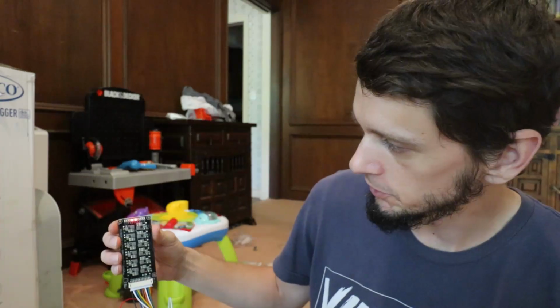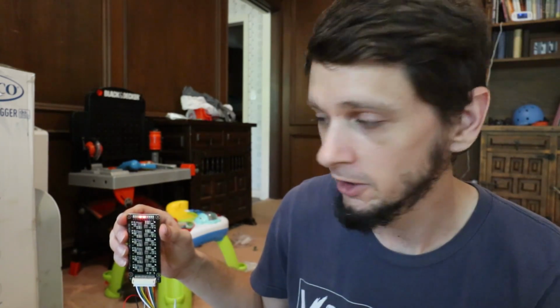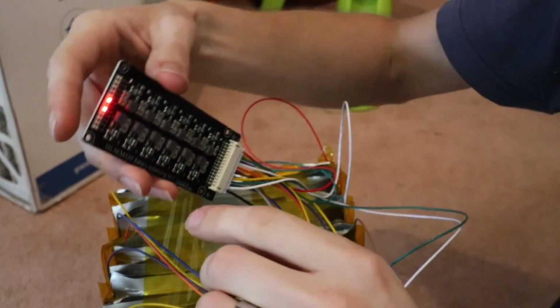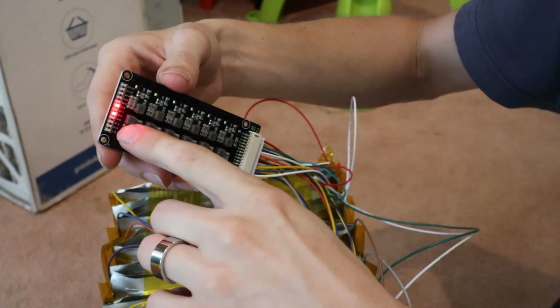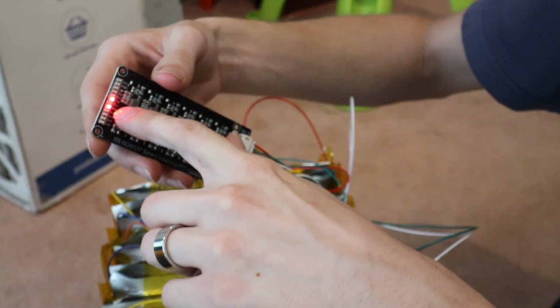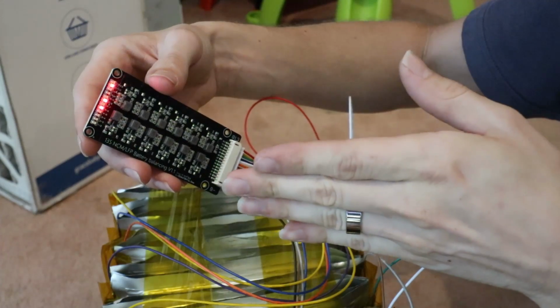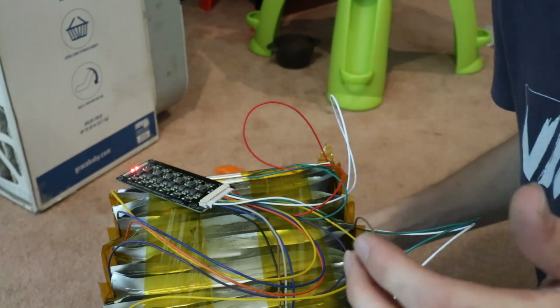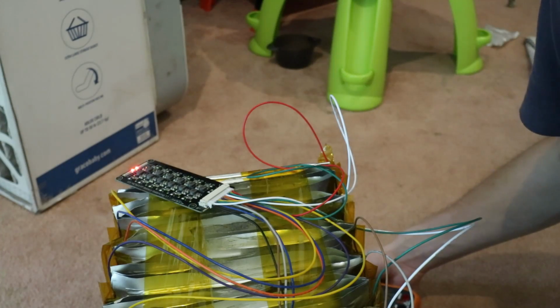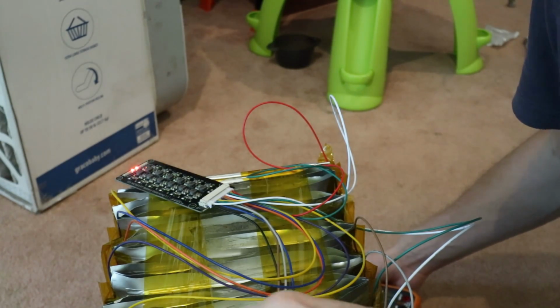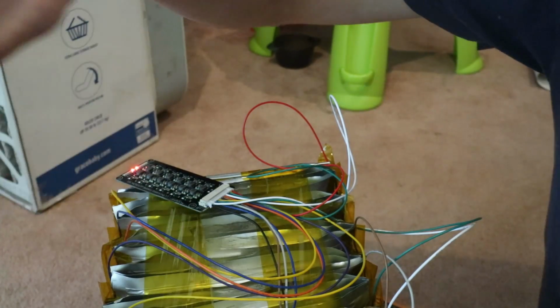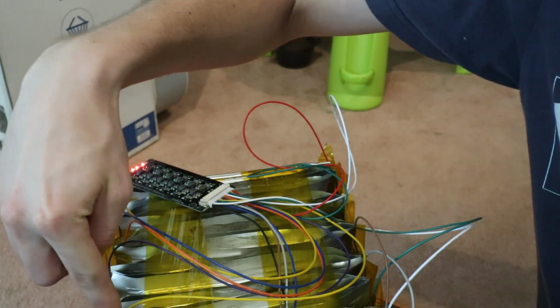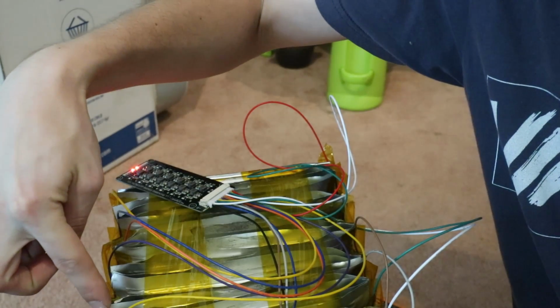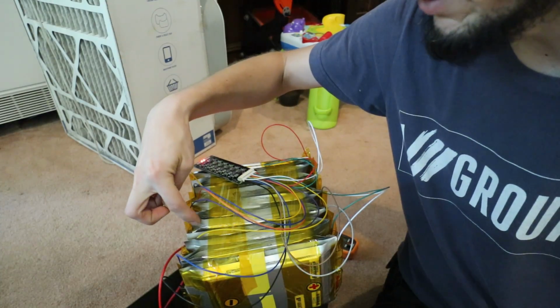So anyway, this is balancing board 2, and I've got it plugged in now. You'll see these little LEDs flashing on and off, and they're labeled, like the first one is 1-2, then 2 to 3, 3 to 4, 4 to 5. You'll see 5 to 6 is currently on, so it's balancing cell 5 into cell 6. This is supposed to do about 1.2 amps worth of balancing. I don't know if that's across the whole board or individual. But if we count my B- as cell 1, we've got 2, 3, 4, 5, so it should be balancing from cell 5 over to cell 6.